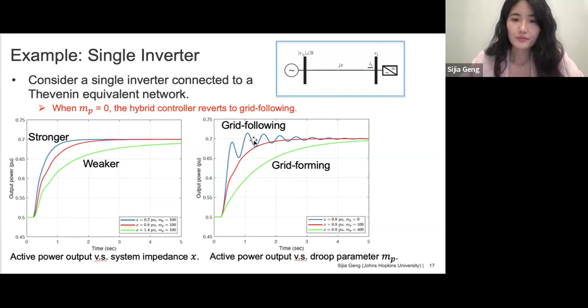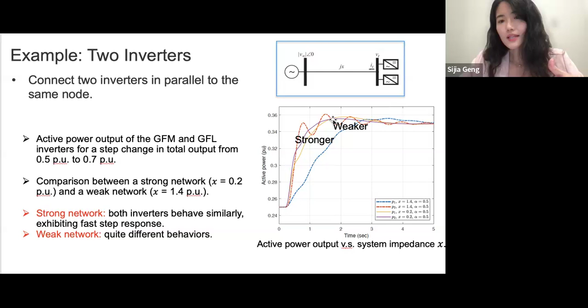overdamped. And this red figure shows the influence of the active power droop parameter on the inverter step response. And we can see that in the weaker grid, the grid following controller is more prone to oscillation and instability. And when we connect both types of inverters to the same bus, we can see that in a stronger grid, they behave similarly to each other, but in weaker grid, they display very disparate behavior, with the following one demonstrating more oscillation.